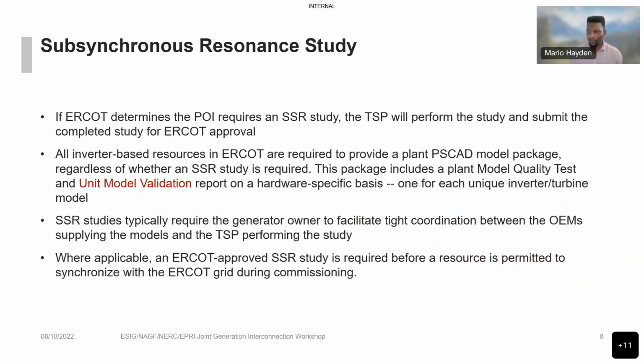So all inverter-based resources in ERCOT are required to provide a PSCAD model package, regardless of whether an SSR study is required. This package requires a model quality test, as well as a unit model validation report, which is a hardware-specific report that looks into each inverter's performance in comparison to the model that's being presented in PSCAD.